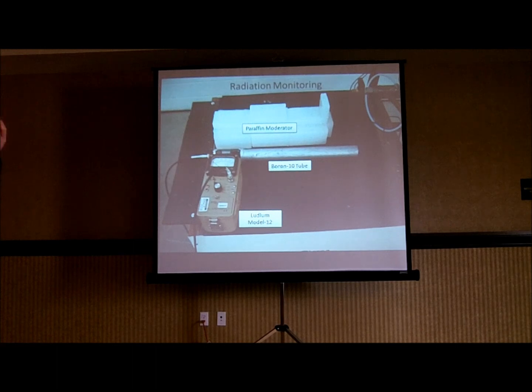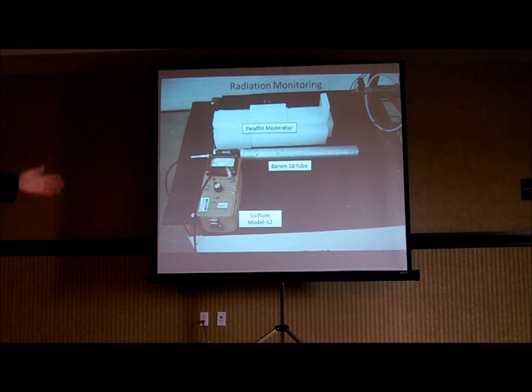The boron 10 decays into a lithium 7 and an alpha particle, and the alpha particle actually produces a very unique signal that this Ludlum Model 12 detects. And this is the primary measurement device of the experiment. So this is critical, that we are able to measure neutrons coming out. One event occurring in a minute is 1 count per minute, 60 in a minute, etc., etc. So I use rate to calculate efficiency.